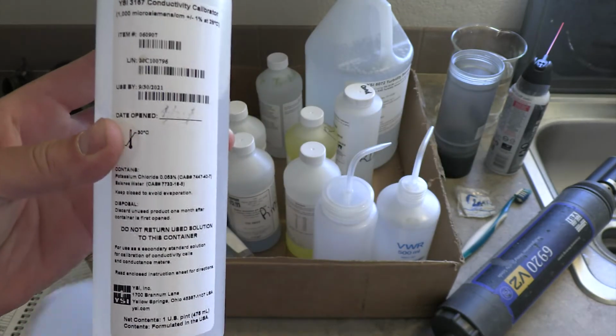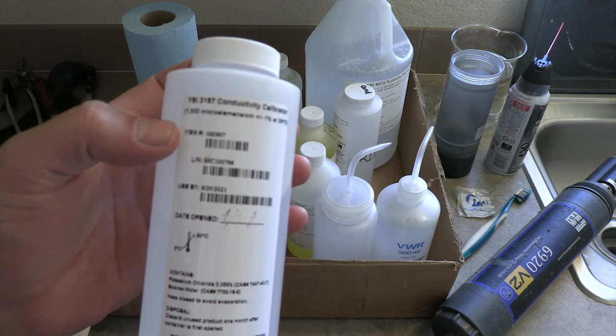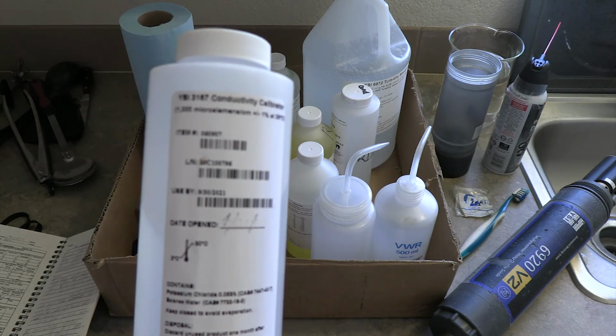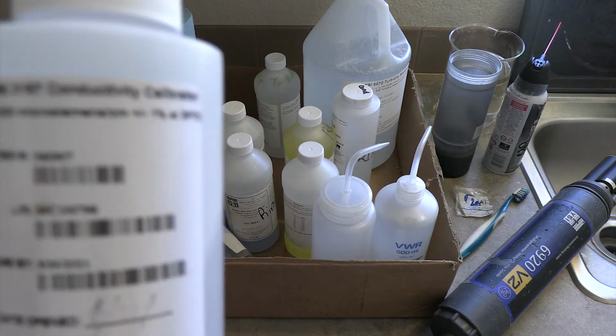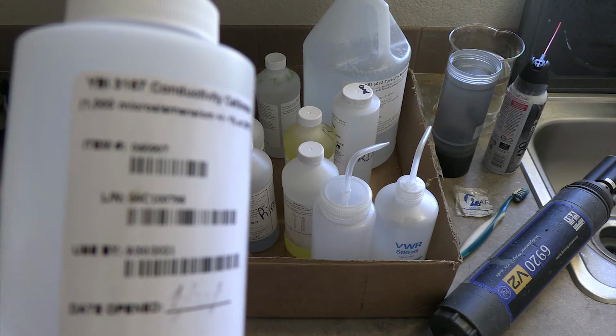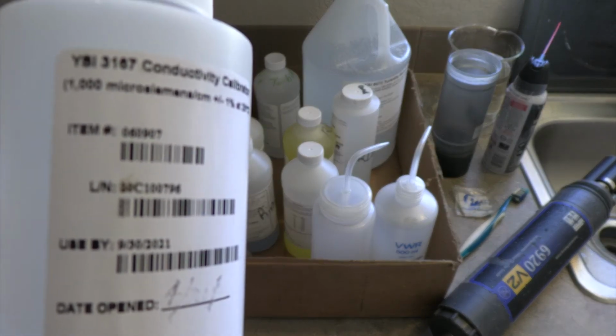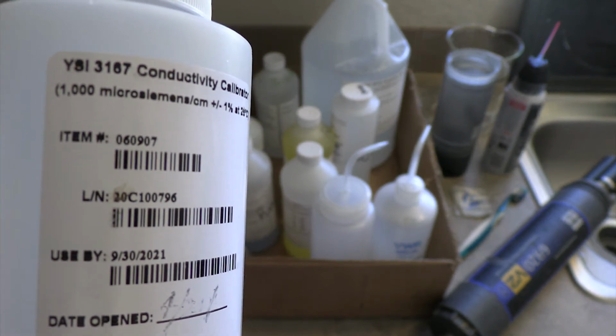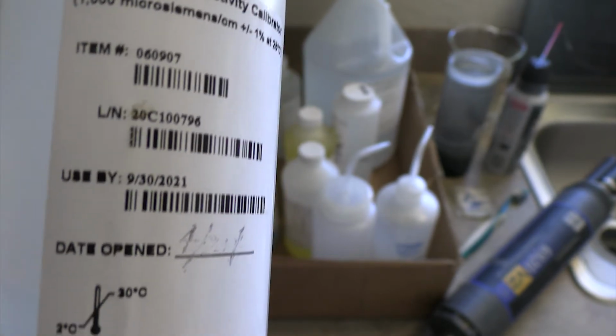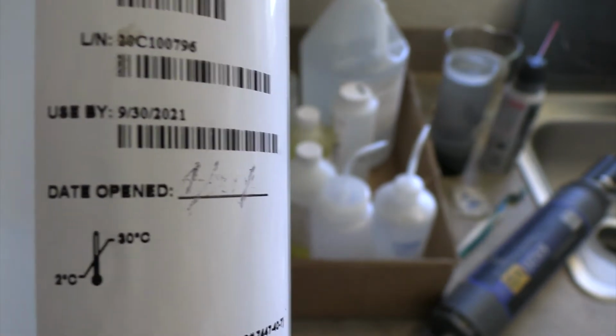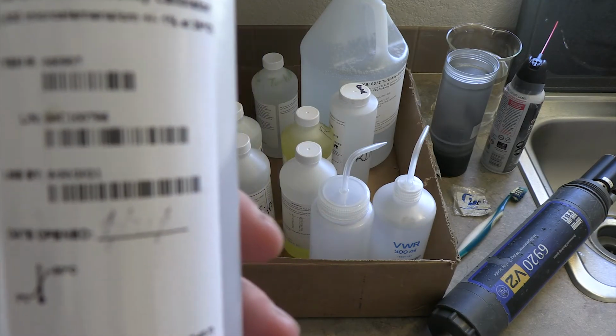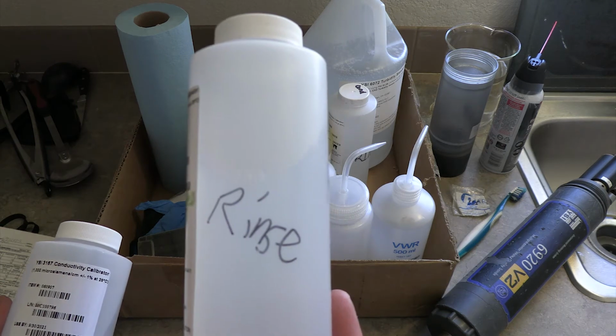And then here we have, on this calibration solution, if I can get it to focus. Okay, so what we have is the item number, which we don't need, and you can see at the top YSI 3167 conductivity calibration. So we need that, and then we need the lot number, this guy right here, and then we need the date used by, which is basically the expiration date. And other than that, that should be good. So some of them are temperature appropriate, but this is not a temperature based solution, and it should be fine. So that's the calibration solution, and then you just make sure you rinse out two times before you actually calibrate.